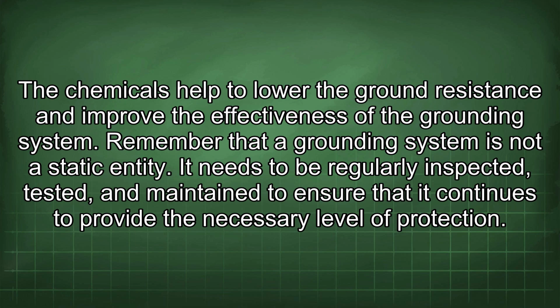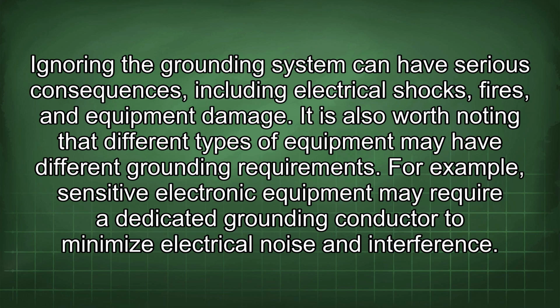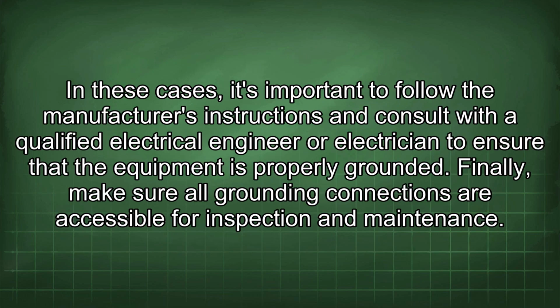The chemicals help to lower the ground resistance and improve the effectiveness of the grounding system. Remember that a grounding system is not a static entity. It needs to be regularly inspected, tested, and maintained to ensure that it continues to provide the necessary level of protection. Ignoring the grounding system can have serious consequences, including electrical shocks, fires, and equipment damage. It is also worth noting that different types of equipment may have different grounding requirements. For example, sensitive electronic equipment may require a dedicated grounding conductor to minimize electrical noise and interference. In these cases, it's important to follow the manufacturer's instructions and consult with a qualified electrical engineer or electrician to ensure that the equipment is properly grounded.